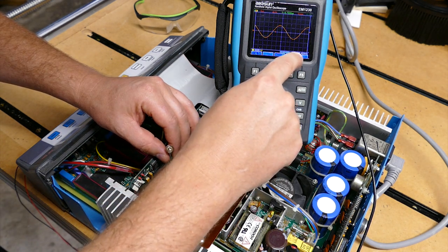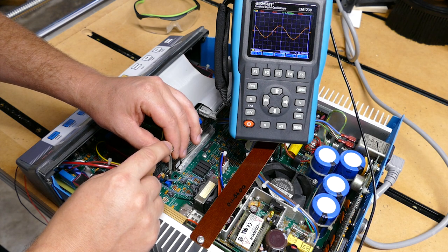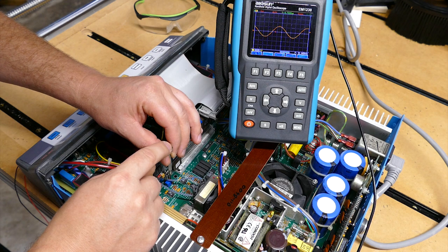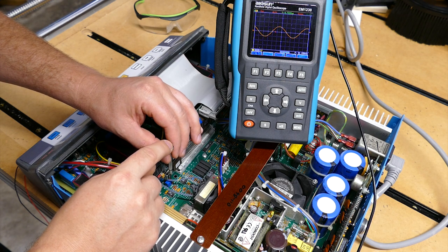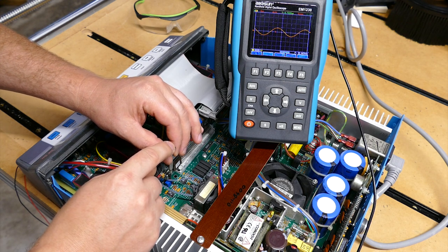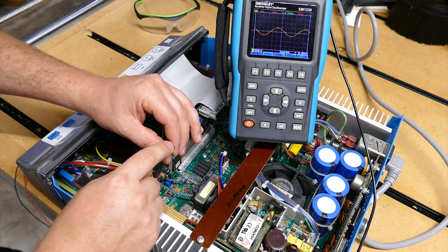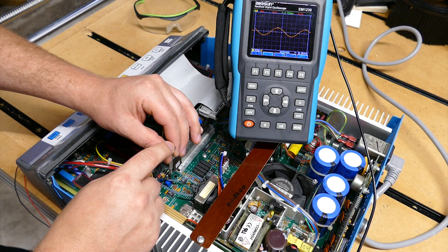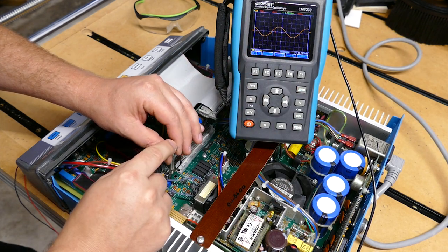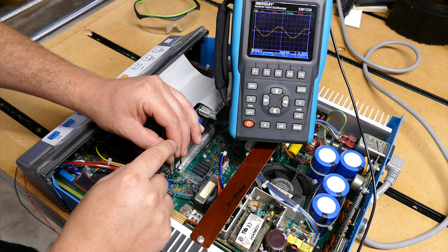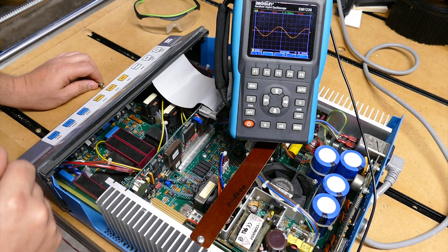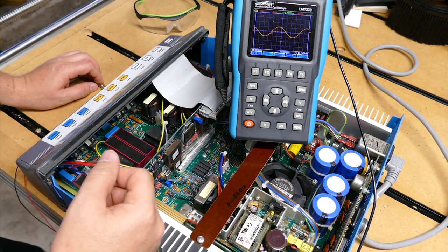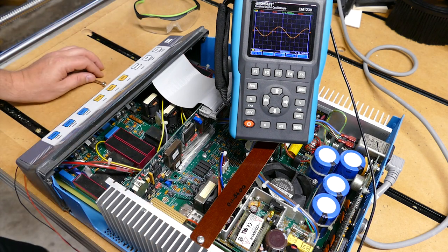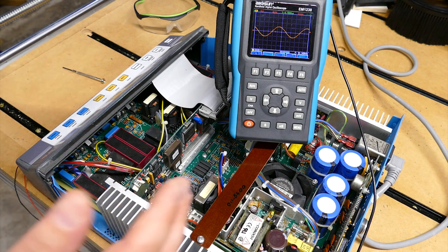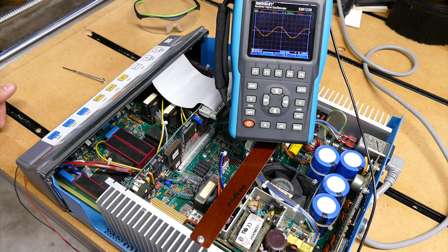It's currently at 80.626 kilohertz, and I'm gonna spin this potentiometer. And the waveform is actually going down, the amplitude of the wave. You can see that as the frequency goes up. So what we found recently is that there is a happy medium between the amplitude of the wave, which is the height of the sine wave, and the frequency. And I found that if I get it around 81.3 to 82 kilohertz, I usually will have a passing unit. So let's go ahead and check it out. I've got it set at 81.348. We're now ready to go ahead and start with our calibration keys.